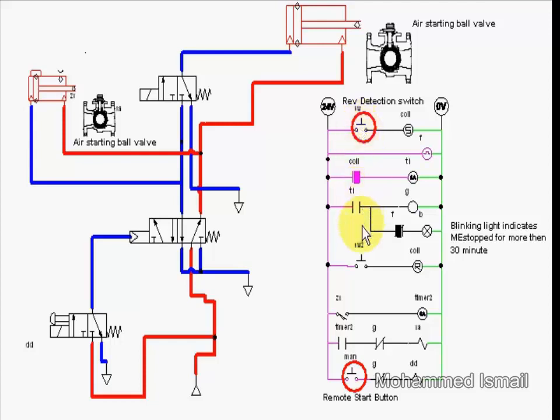In the starting sequence, when the starting push button is pressed, first air goes to the slow turning valve which turns the engine to a specific revolution for a specific time. When the slow turning phase is finished, the main air starting valve is signaled to open to supply the required starting air.